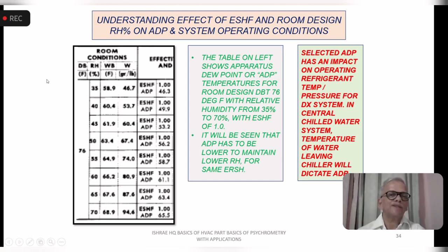What I've done here is I have taken 76 degrees as the room dry bulb temperature, with relative humidity changing from 35 to 70% in steps of 5. And I have selected an effective sensible heat factor of 1 as a sample, which means all the heat to be removed is sensible. There is no moisture removal required in the particular application. Maybe this is true for many of the server rooms. It could be up to 98% or 99%. I have taken 1 just to understand the effect.